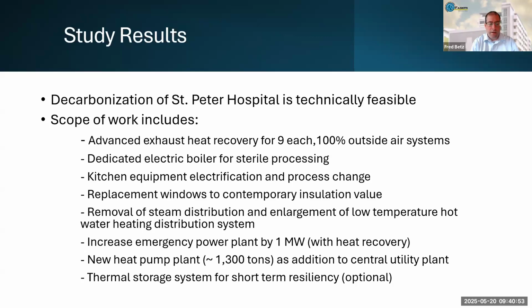Our cost estimators and construction consultants helped guide us towards an alternate solution: to build an addition to the central utility plant to the south, rather than building on top of it. One is being less disruptive, but two, it actually ends up being cheaper. That was a bit surprising to me, but the numbers bore that out. We also opted to add an electrical service, but let me be clear here, we're not adding load to the grid, right? Within this cost, there is an additional electrical service. Essentially we're decanting a whole bunch of load off of the existing electrical service and moving it to the new electrical service. So the net is not increased on to Puget Sound Energy's load. But it was actually simpler to just put a new service in and build this plant separately rather than try to splice it in with the existing plant. So something to be considered, again, on a case-by-case basis.